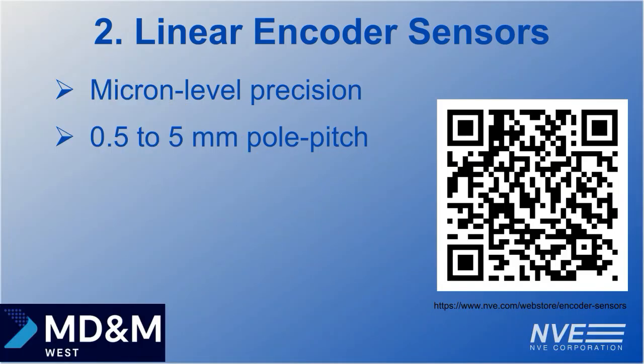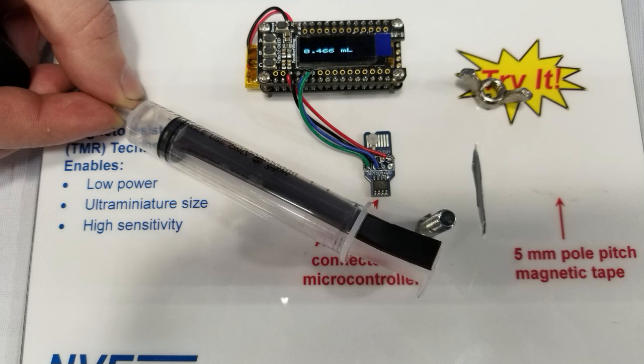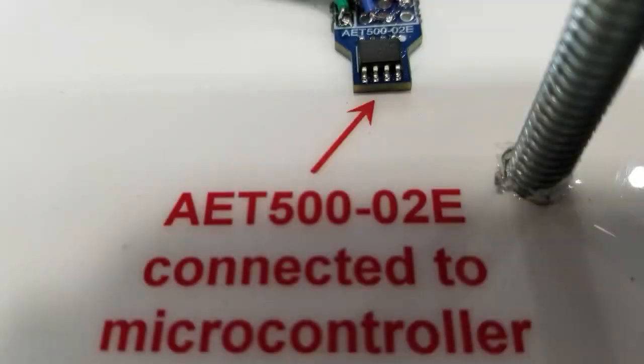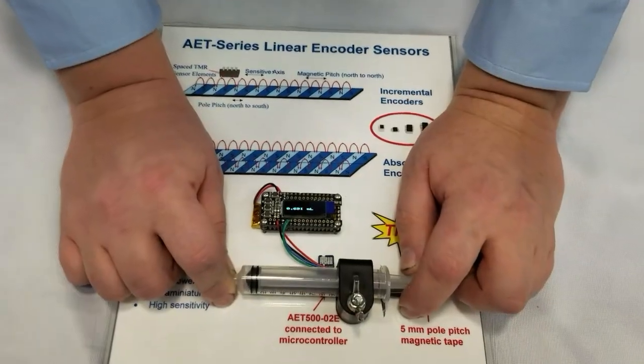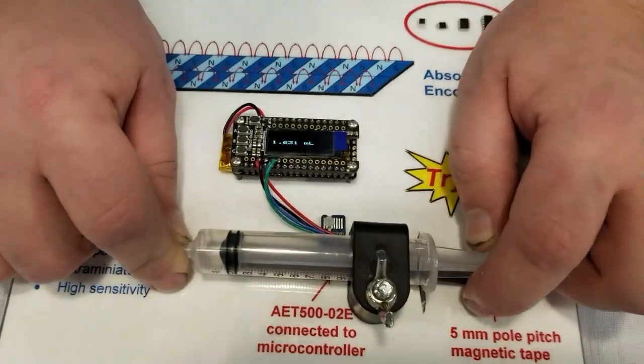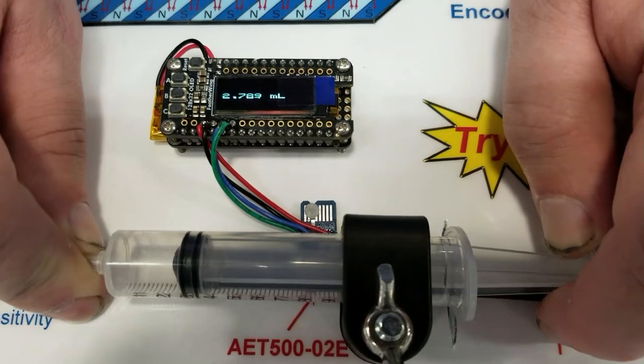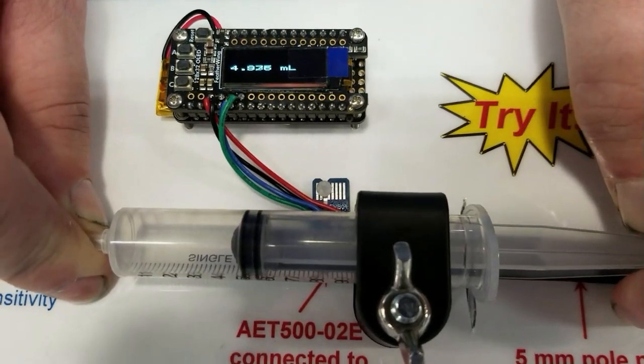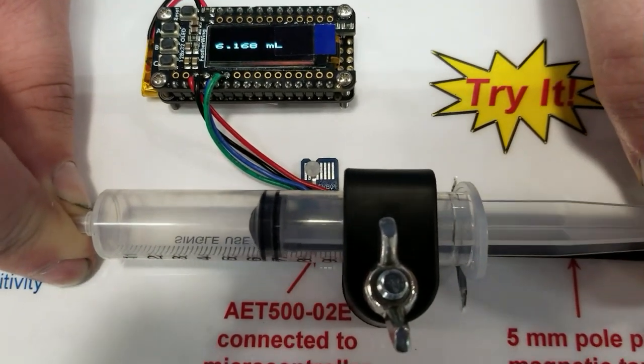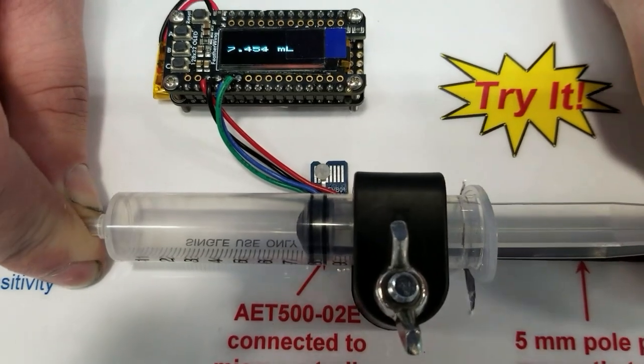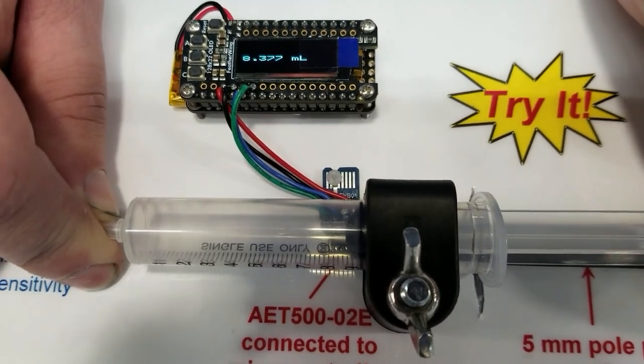The second demo is a linear encoder syringe pump. A magnetic scale tape is attached to the syringe plunger. The sensor detects the scale tape magnetic poles and interpolates between the poles. This is very precise, with a resolution of 10 microns, or 1,000th of a milliliter for the 10 cc syringe. This type of sensor can inject precision into a variety of linear motion applications.